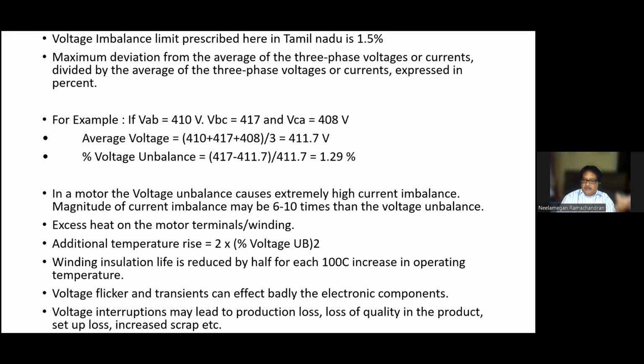So voltage flicker and transients can badly affect electronic components. See, recently, about 6 months or 10 months before, my computer packed up because of this flicker. Then voltage interruption may lead to production loss of product. Once the power goes off, if it comes back after 1 hour or 2 hours or 8 hours, it doesn't matter, because we have a backup generator, we can switch it on. But with interruptions, where power goes and in 2 minutes it comes again, the electrician is in a dilemma whether to switch on the generator or not. So you switch on the ACB, then again it trips. These kinds of interruptions do more damage than power failures.